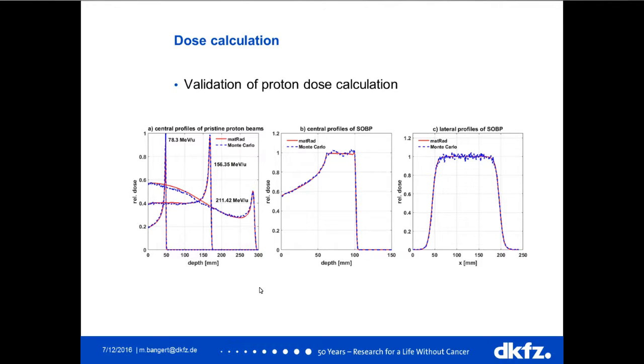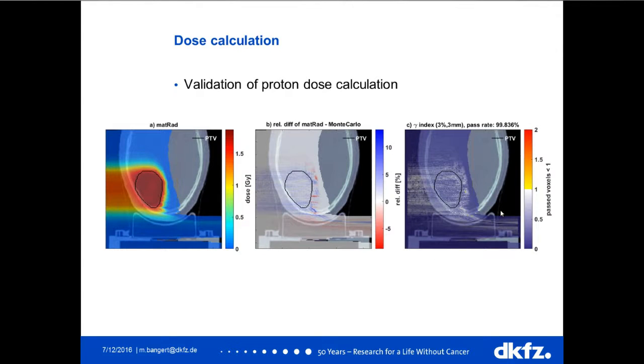For particle dose calculations we use a conventional pencil beam algorithm factorizing into lateral and depth-dependent components. The lateral component can be either a single Gaussian or a double Gaussian to describe the lateral dose fall-off. We validated this algorithm against Monte Carlo simulations of the HIT beamline, showing results for pristine pencil beams, SOBP depth dose profiles, and lateral profiles through the SOBP. We're quite happy with the agreement, which is reflected in high passing rates for gamma index comparison for patient cases.